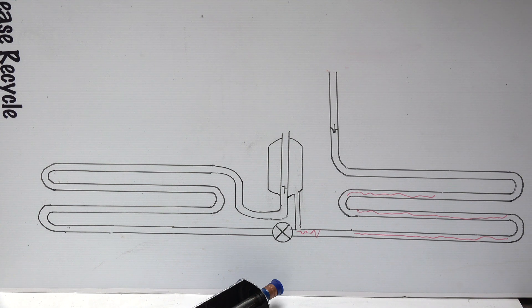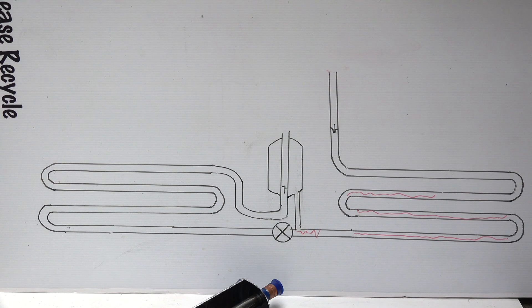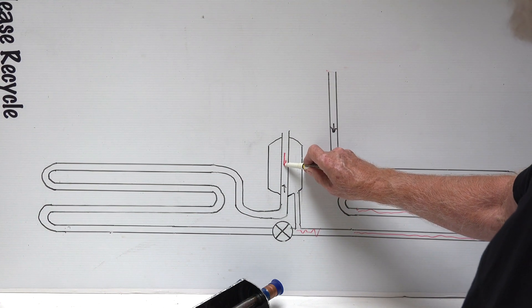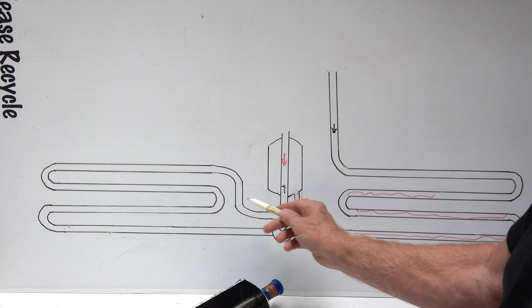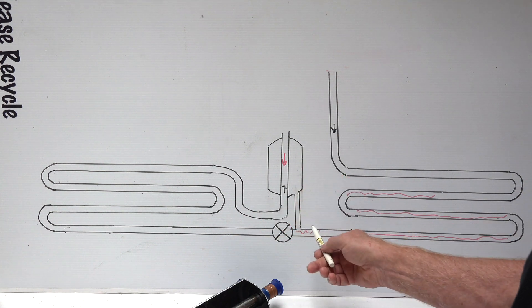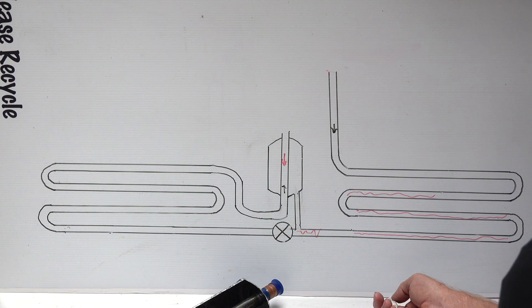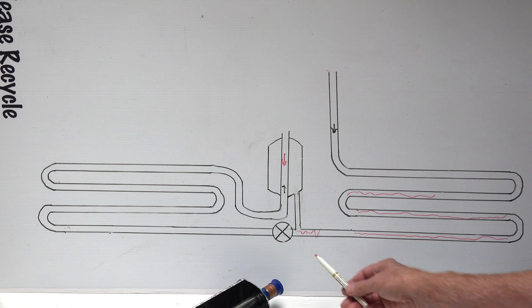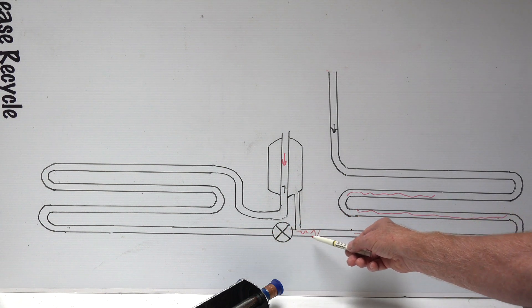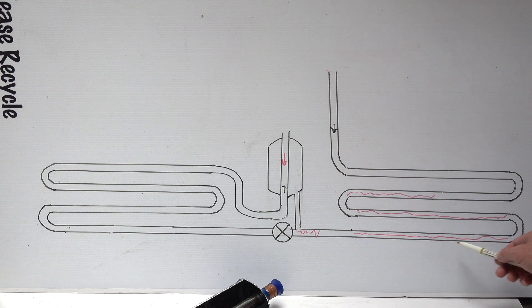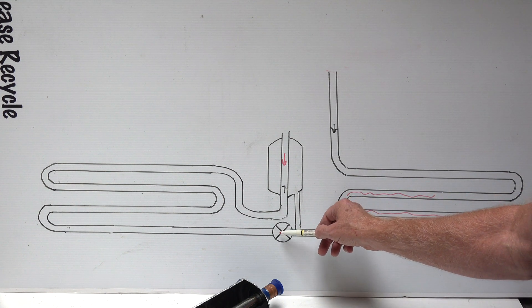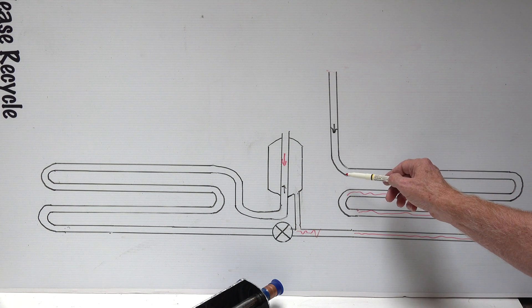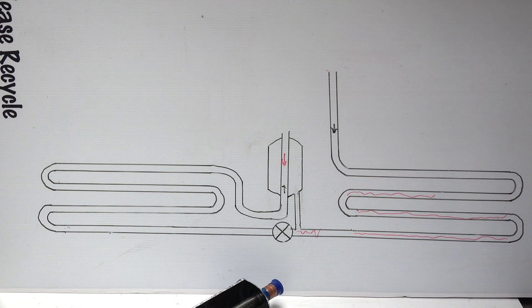Now what happens when this thing goes into defrost? Well, all this stuff reverses. We will now have the refrigerant moving this way because this is a discharge line, and what it's going to do is heat this thing up and it's just going to shove that refrigerant back in there. If we also have a TXV for the indoor coil, then the refrigerant will come back like this. Refrigerant will dump in here, and as it goes through, this valve is going to throttle when the superheat goes down.